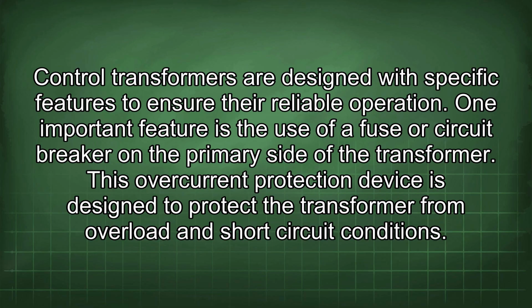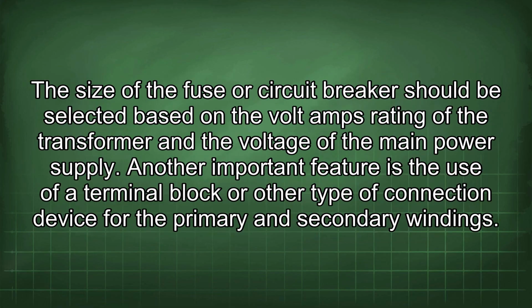Control transformers are designed with specific features to ensure their reliable operation. One important feature is the use of a fuse or circuit breaker on the primary side of the transformer. This overcurrent protection device is designed to protect the transformer from overload and short circuit conditions. The size of the fuse or circuit breaker should be selected based on the voltamps rating of the transformer and the voltage of the main power supply. Another important feature is the use of a terminal block or other type of connection device for the primary and secondary windings.